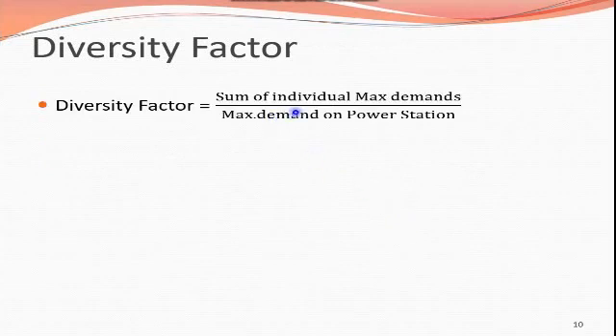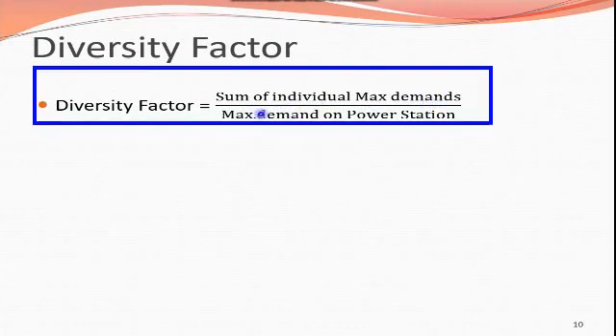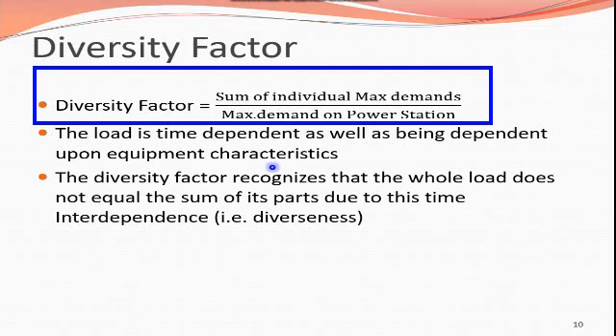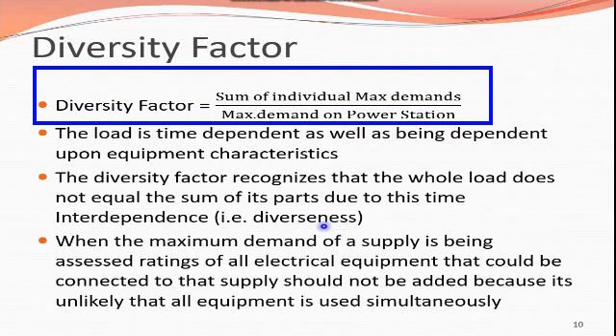Diversity factor equals the sum of individual maximum demands divided by the maximum demand on the power station. The load is time-dependent as well as dependent upon equipment characteristics. Diversity factor recognizes that the whole load does not equal the sum of its parts due to time dependence. When assessing maximum demand, ratings of all electrical equipment should not simply be added, because it is unlikely that all equipment is used simultaneously.